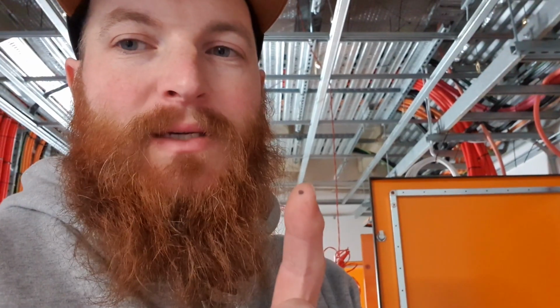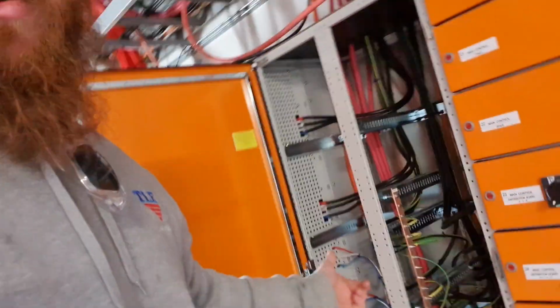What was happening is that one of the neutrals in one of the sub-circuits must have been touching one of the medical services panels, which are bonded. Basically anything in there that's a neutral could have been touching an earthed panel, and that's given us a fault - essentially it is a fault at this point. None of the stuff is fitted off, mind you, so it's completely fine.